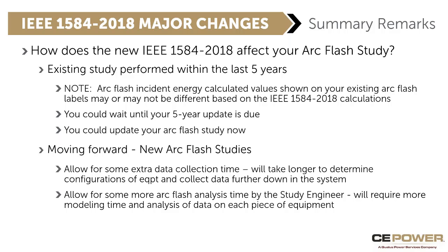Things to be conscious of is that you should allow for some more data collection time, because we don't have that transformer exception anymore. We have to go and get that data now. And we also have to think more strategically and do more planning for things like electrode configuration. So that can add to some analysis time. And so that is the material that I have prepared for the 1584 update.